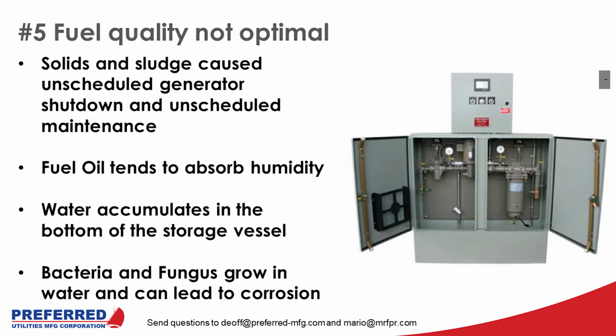One of the reasons for this sludge buildup is microbial attack. This microbial growth is accelerated by our warm weather and humidity, so it's prevalent in the area. Many industrial and commercial sites since Hurricane Maria now began installing automatic fuel filtration sets. These units are self-contained and automatic. They're able to remove water, suspended rust, dirt, and other contaminants that could affect the engine, and they help maintain the quality of the stored diesel fuel. This is particularly important in sites where the only user of fuel is the auxiliary genset. So if you have a large amount of fuel stored on your site, but you're not recycling it frequently, a fuel filtration set is recommended.